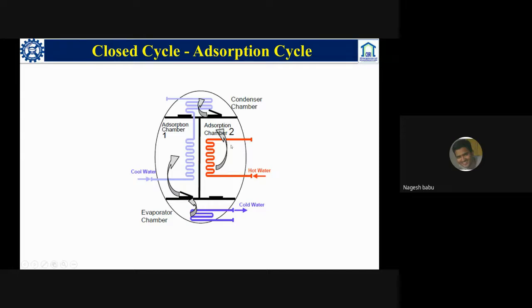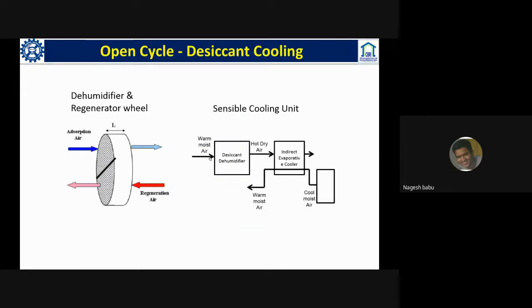But both of these are closed cycles, meaning they operate under low pressure, not at atmospheric pressure but at a lower pressure. Whereas we are going to briefly discuss the open cycle, that is desiccant cooling. In desiccant cooling, we have systems which operate at atmospheric pressure. The advantage of operating at atmospheric pressure is that no pressure sealing is required, so the typical system cost also gets reduced.